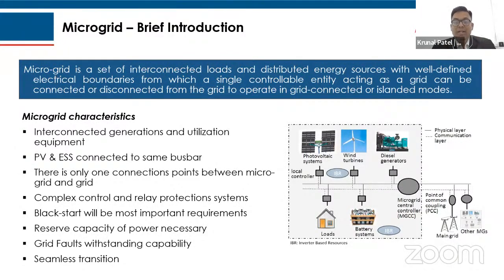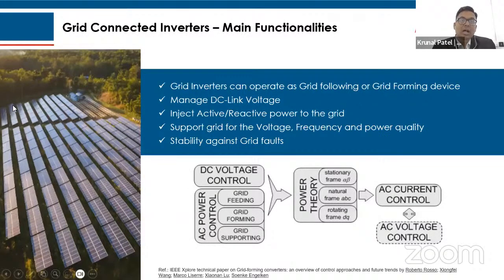So moving further, in my next slide, I wanted to cover grid-connected inverters. There are some main functionalities. As you can see, grid-connected inverters can operate in either grid following mode or grid forming mode. This type of inverter should manage the DC link voltage. For a PV inverter or a battery inverter, the input is on the DC side, so that DC link voltage should be maintained. For that, enough power electronics are required to adjust these voltage ranges.